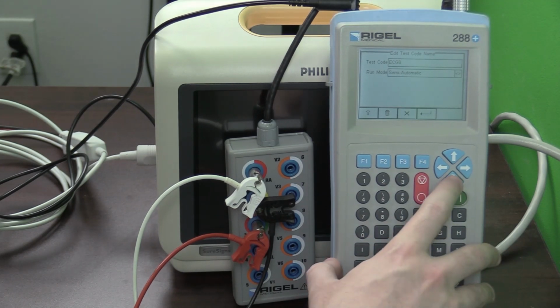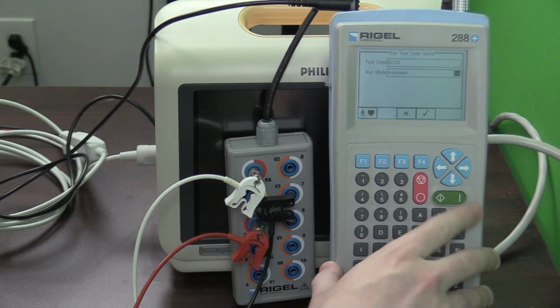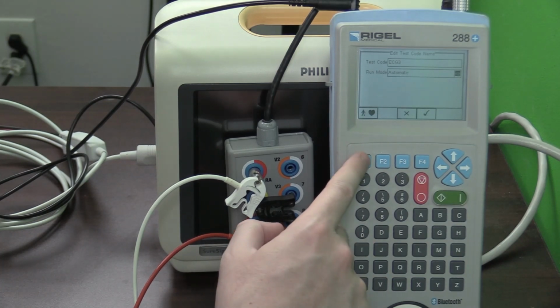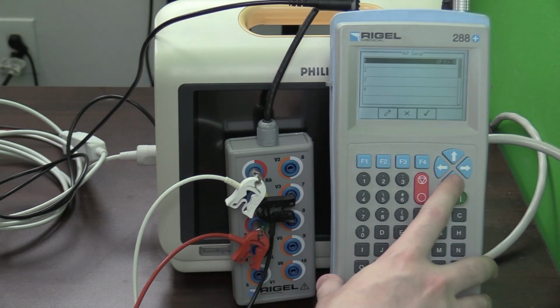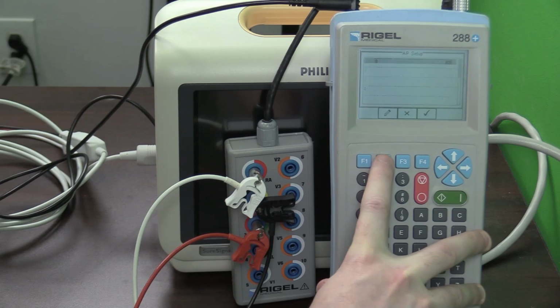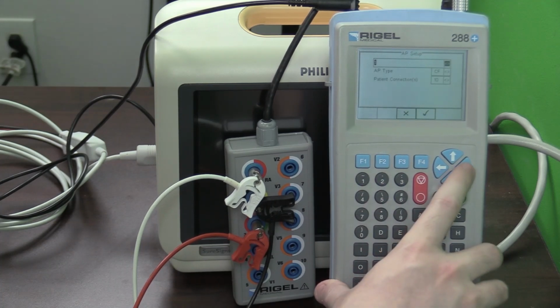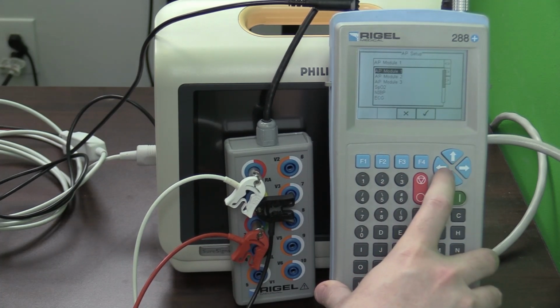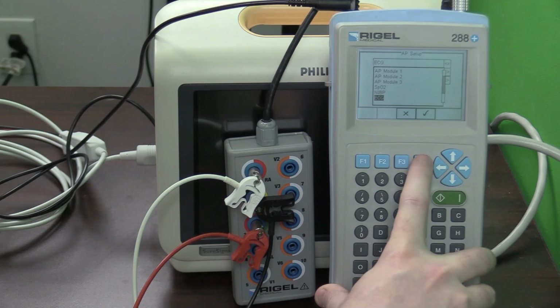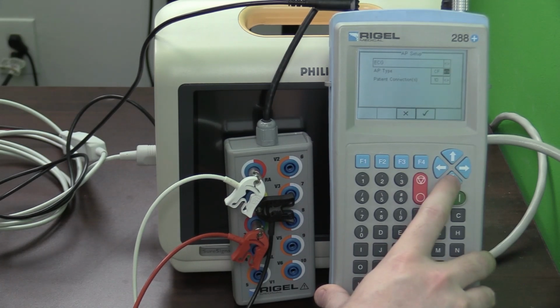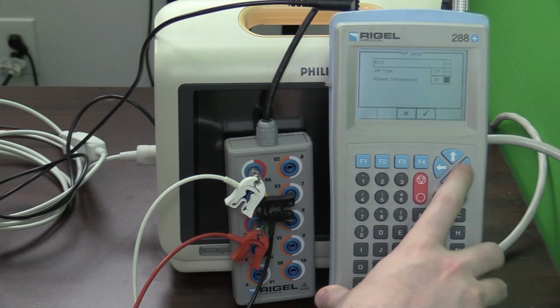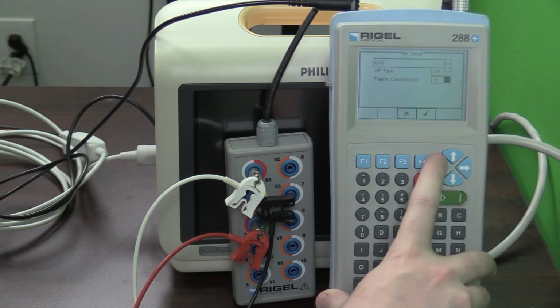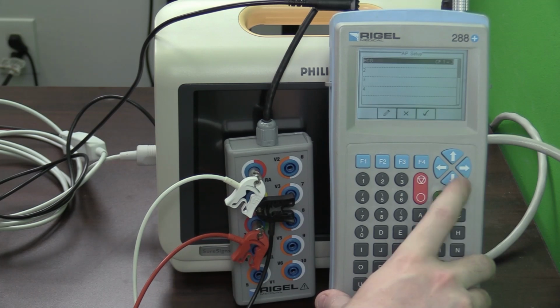After I've created that, I'm going to scroll down and make it an automatic test and hit F1 to get your specific applied parts. Select F2, and for me, I'm testing an ECG right now, so I'm going to make it an ECG applied part by scrolling down and selecting F4 over ECG. And I only have a 3 lead right now, so I'm going to select 3, and you can do up to 10 leads. Select F4 to save your changes.